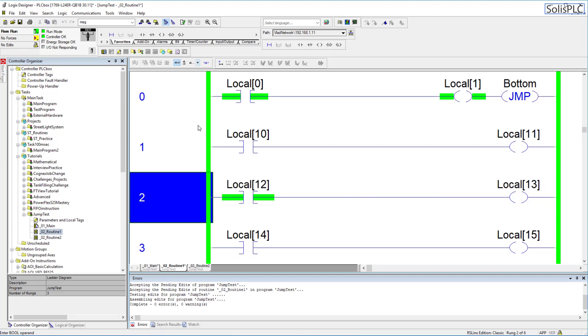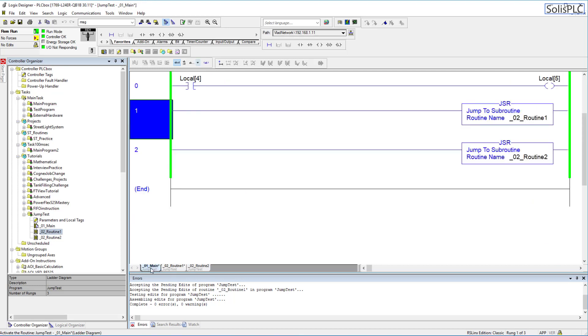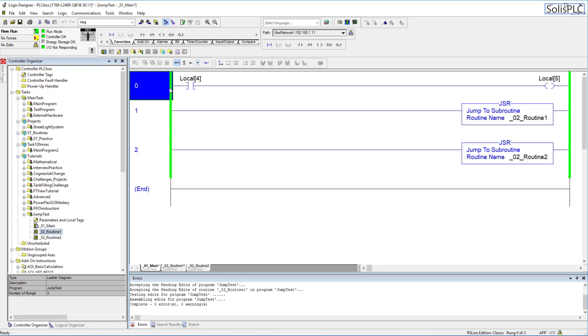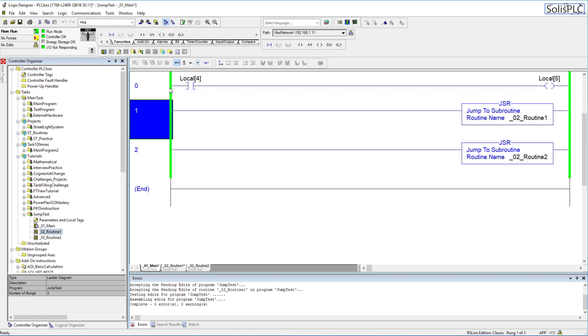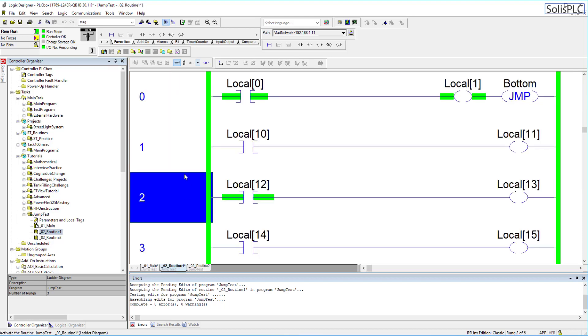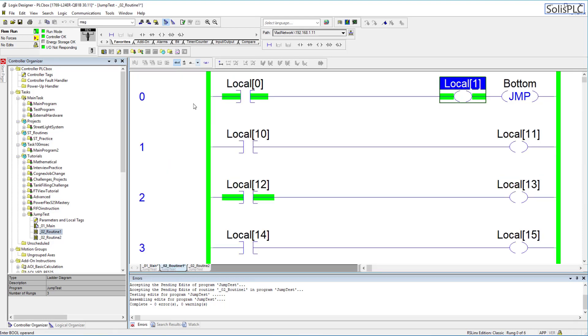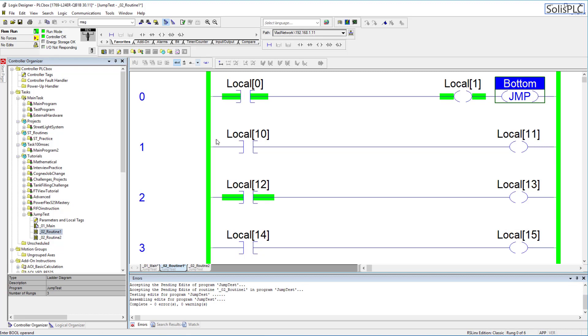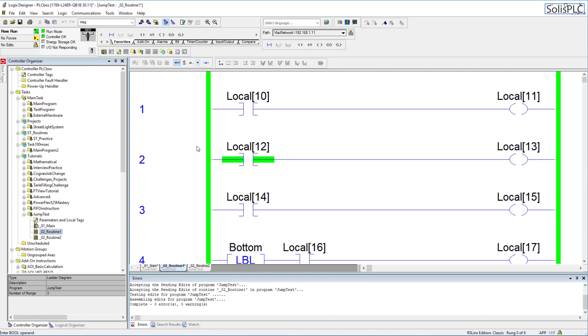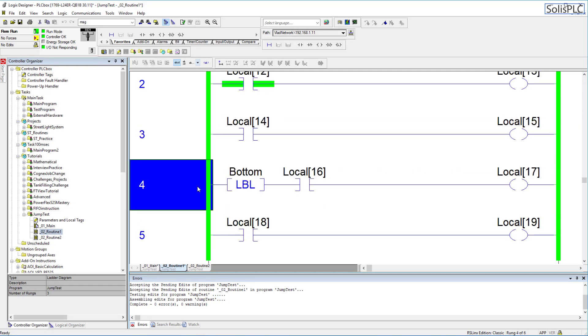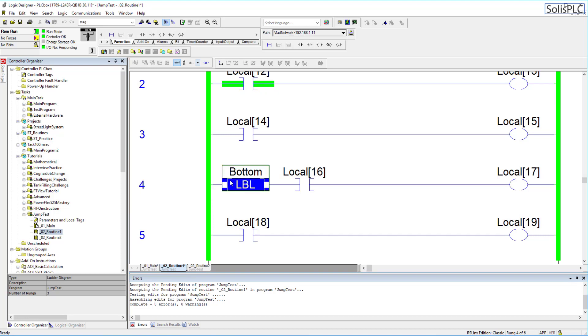Now what's truly happening is that let's go back to the main function and analyze this so the PLC starts to scan this routine which is the main routine as specified by the program it starts at rung 0 which doesn't have anything exciting it starts at rung 1 then it goes into the JSR now let's go into routine 1 and you'll notice that since this is true we're going to energize this OTE and we're going to energize this JMP now this JMP what it does is that it immediately skips through all the rungs and goes to where the label belongs so in this case it's going to go into this rung 4 and it's going to continue executing starting from this rung.